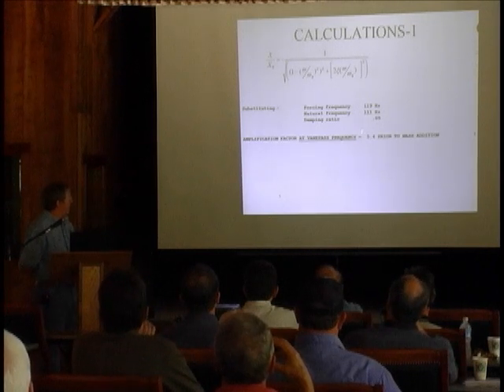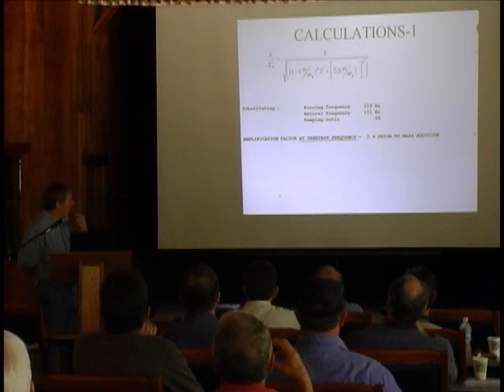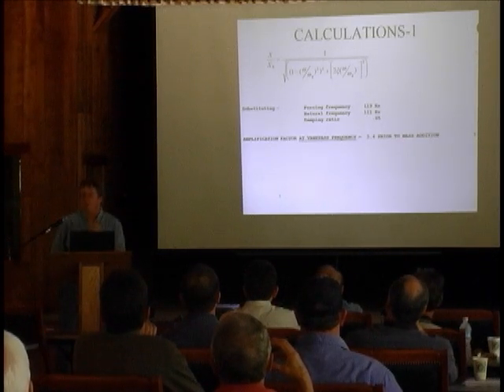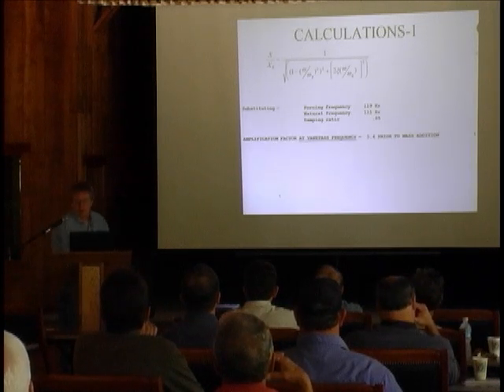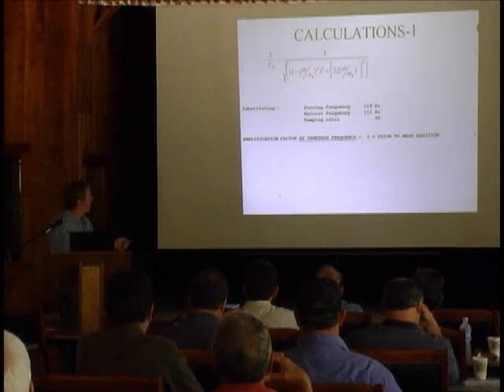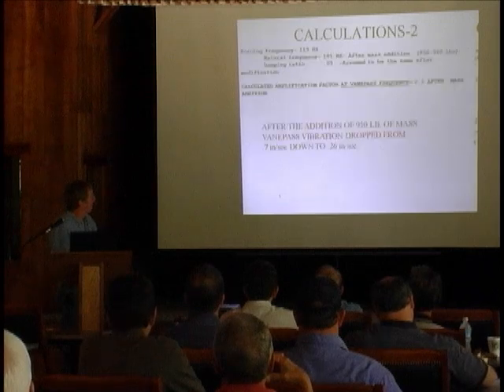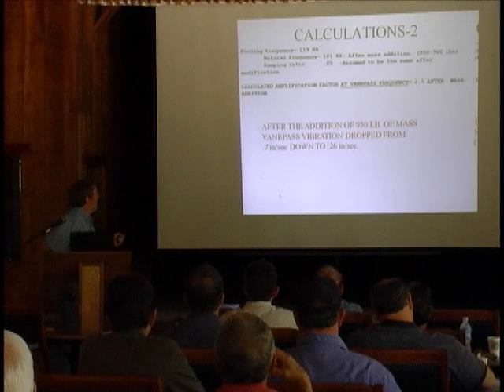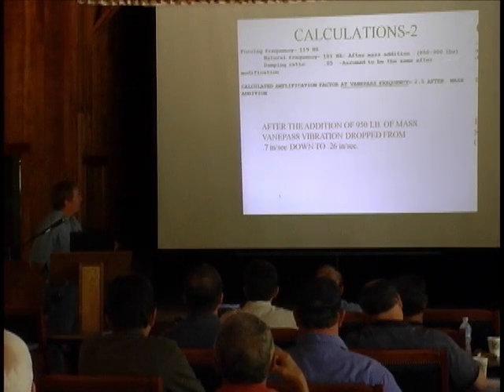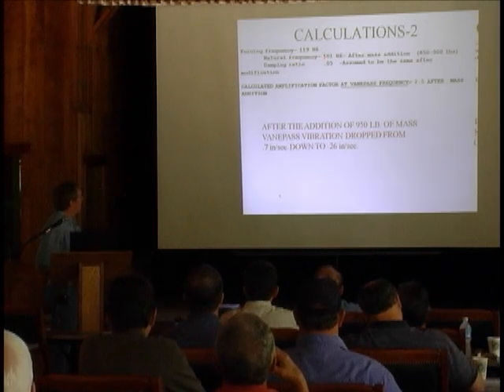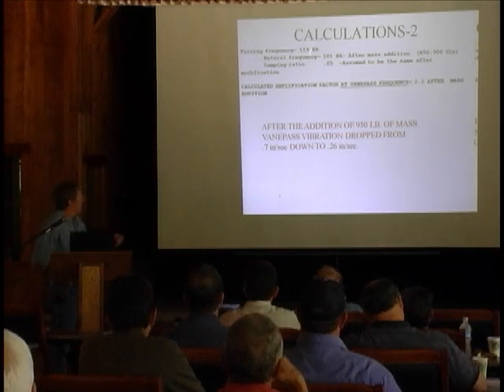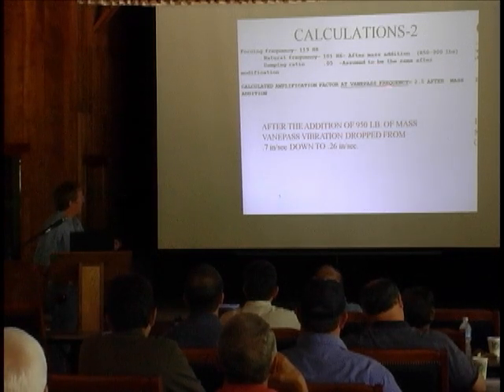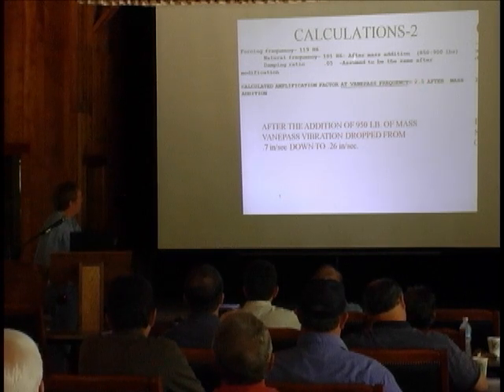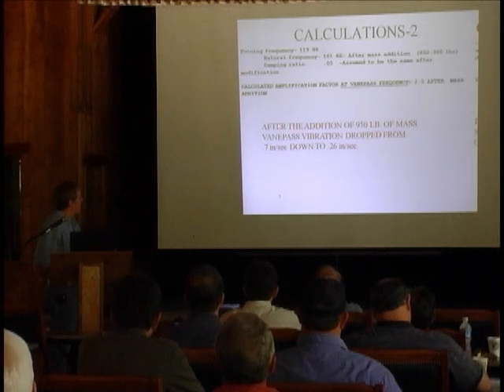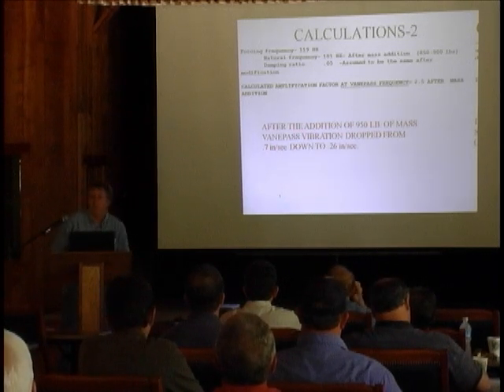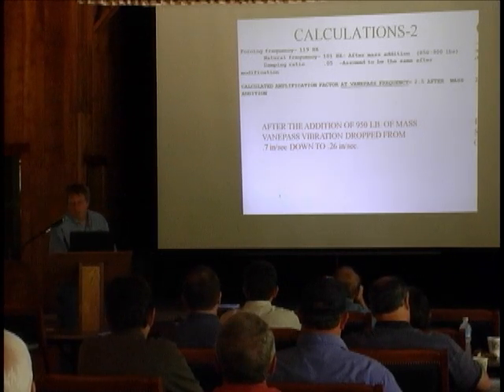So anyway, I found out the amplification factor at vane pass was 5.4. And I said, wow, if I can get rid of this, I can get us way below what the requirements are. So what I decided to do was alter the natural frequency by adding mass. After the mass calculations, if we put in 850 to 900 pounds, that would drop the natural frequency to 101. I assumed the damping ratio would be the same, and calculated it at vane pass, and it came out 2.5 if I did this particular thing. So they added the 950, and it went from 0.7 inches a second down to 0.26, which was very, very acceptable for this.